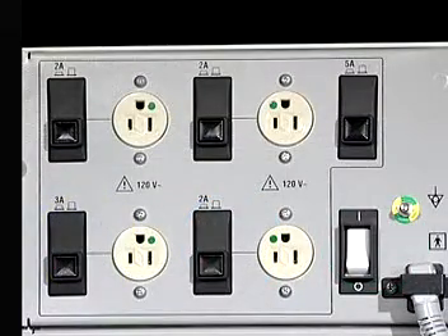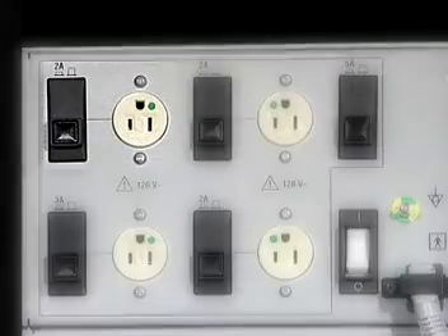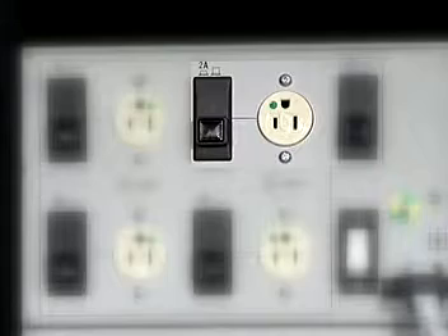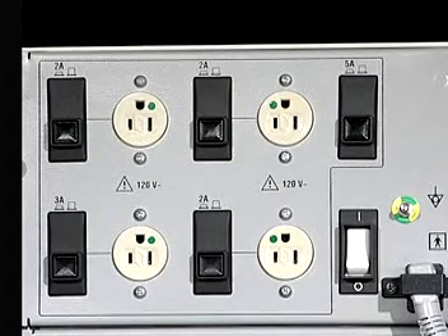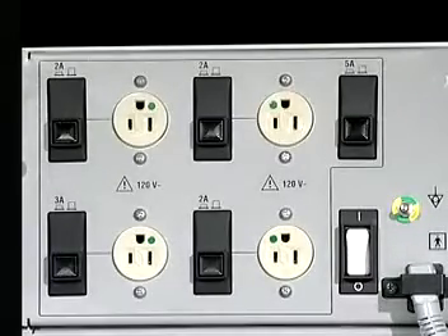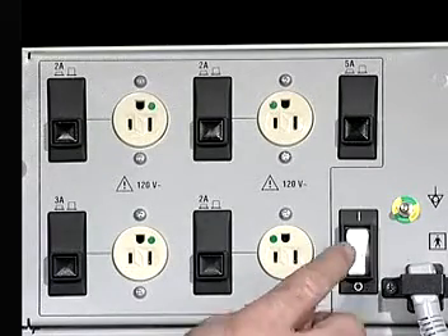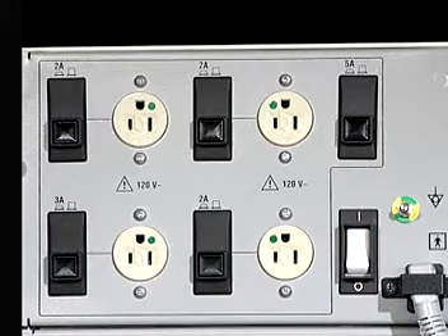4 optional electric outlets can be ordered with the Anesthesia. They are protected by 2 and 3 amp circuit breakers and the entire bank of 4 outlets is protected by a 5-amp circuit breaker. A resettable circuit breaker switch is also located in the vicinity of the outlets. Failure to have the circuit breaker switch in the on position will cause the ventilator to operate on battery.